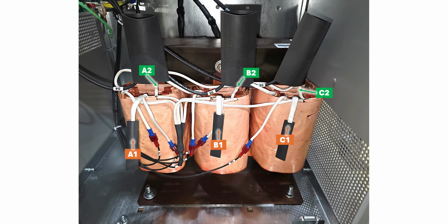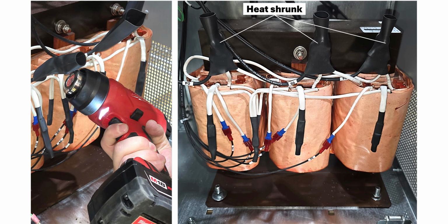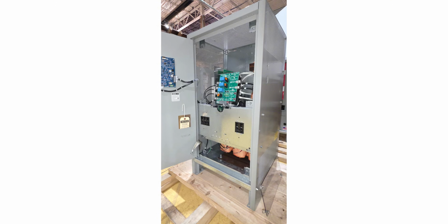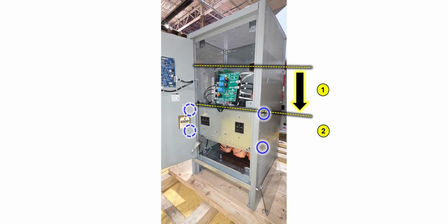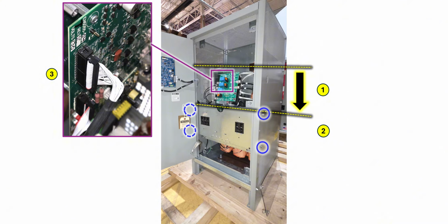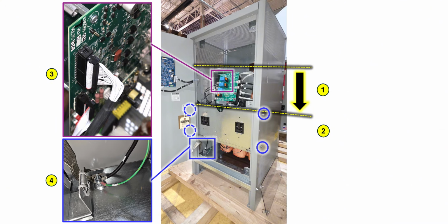Now's the time to shrink wrap all our new tap connections that include wires A2, B2, and C2, as well as the unused wires A1, B1, and C1. The voltage conversion is complete. Now, you can reconnect the parts of the charger that needed to be moved to access the transformer. Number 1, cut the zip ties holding the breaker bracket. Number 2, mount the breaker bracket to the charger with the fasteners on each side. Number 3, reconnect the ribbon cables to the power board. Number 4, reconnect the grounding wires 10 and 47 to the ground bolt on the chassis.